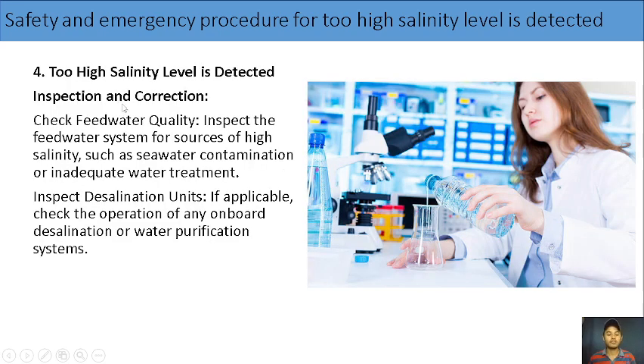So next is inspection and correction. Check for feed water quality. Inspect the feed water system for sources of high salinity such as seawater contamination or inadequate water treatment, or maybe your source already has high seawater or salinity. So inspect desalination units. If applicable, check the operation of any onboard desalination or water purification system. Maybe your freshwater generator has so much scale or there is a problem in the vacuum. That's why there is very high salinity in our water. So check it and rectify the problem.